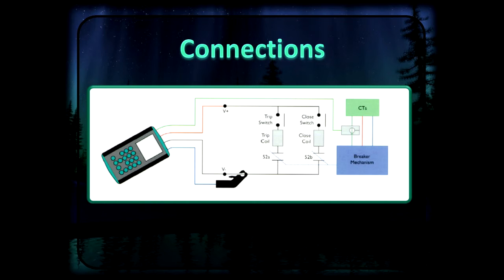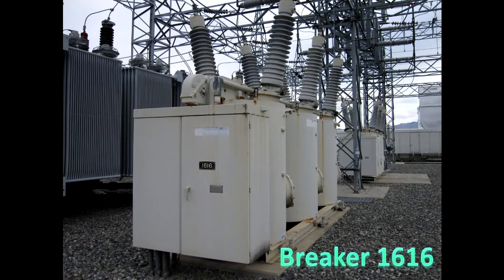So the example we're going to do here is a Westinghouse breaker. This is an oil breaker. It has an air pneumatic operating system. This is actually breaker 1616 at the International substation. It's a 138,000 volt breaker.